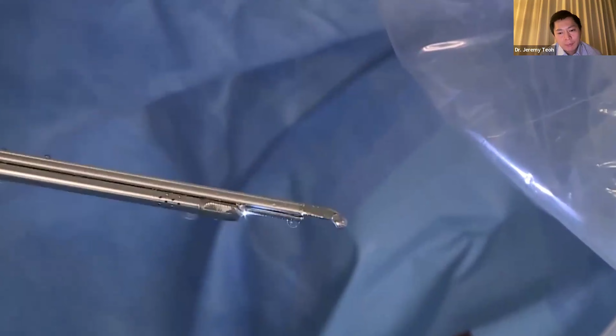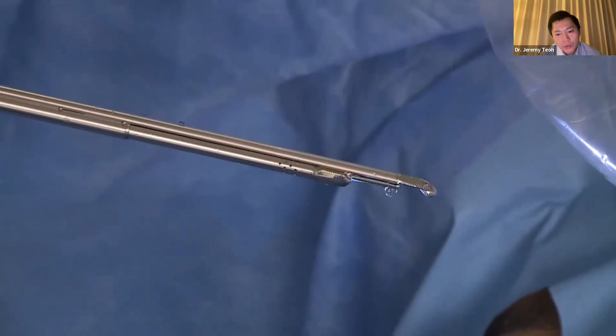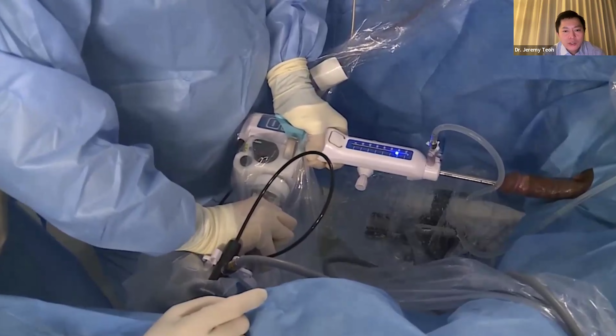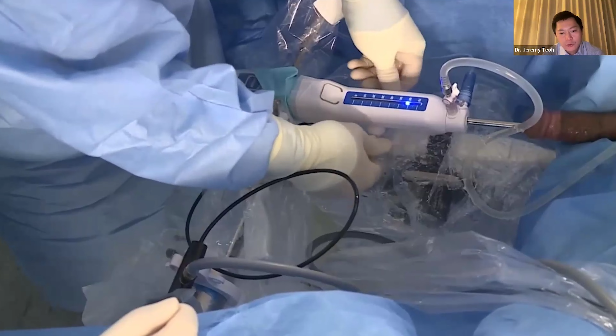So now we're trying to prime the device, making sure that there are no gas bubbles in the tubes. And then we want to make sure that we can rotate the knob in order to retract the lens. So here you can see we're retracting the lens, and on top you can see the tip of the cystoscope as well as the water nozzle. And now we would insert the device into the bladder neck and then try to fix it to a holder here. Basically one holder on the left is for fixing the ultrasound. The other holder on the right is for fixing the water jet delivery device.